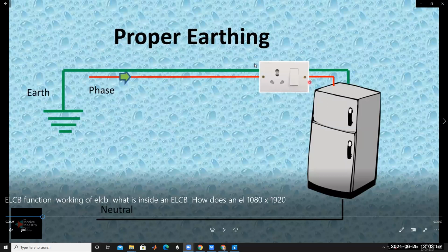For proper earthing, that means there is no leakage current. This is a fridge. This is the phase and neutral, phase connected and neutral connected, and this is the earth wire, connected here like this. Under normal operating conditions there is no leakage current. In the proper earthing condition, the current entering the phase terminal and the current coming back to the neutral terminal are the same. Phase current and neutral current are equal, for a single phase supply.